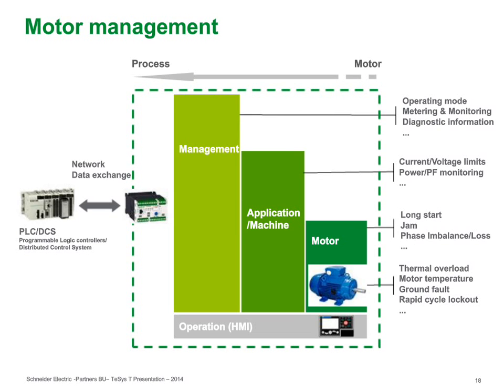And then finally, at the high level here, if you set up the metering and the monitoring for alarms that will tell you when your equipment is running out of norm, this can be part of the process management that goes along with your facility, based on the data that, again, you get out of this unit, being the TeSys T Motor Manager.